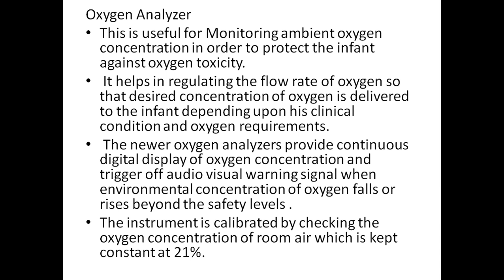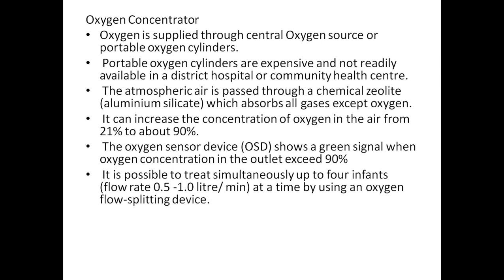The atmospheric air is passed through the chemical zeolite, which absorbs all gas except oxygen. It can increase the concentration of oxygen in the air from 21% to 90%. The oxygen sensor device shows a green signal when the oxygen concentration at the outlet exceeds 90%. It is possible to treat up to 4 infants simultaneously by using an oxygen flow splitting device. The equipment is provided with 4 filters to eliminate dust, humidity, and bacteria.